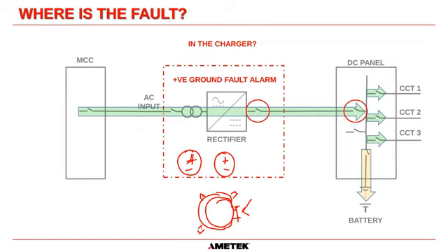What tends to happen is that getting to this screw can be an absolute pain. So a lot of people just loosen it as much as they can, and then wiggle the old capacitor out. Then when they put the new capacitor in, they wiggle or screw it in. What that can do is cut the insulation on one of the DC capacitors. If you cut through the insulation and the can of the capacitor touches the clamp, well, the can of the capacitor is actually connected to the negative terminal of the capacitor. So you will create a ground fault if the insulation on that capacitor has failed.